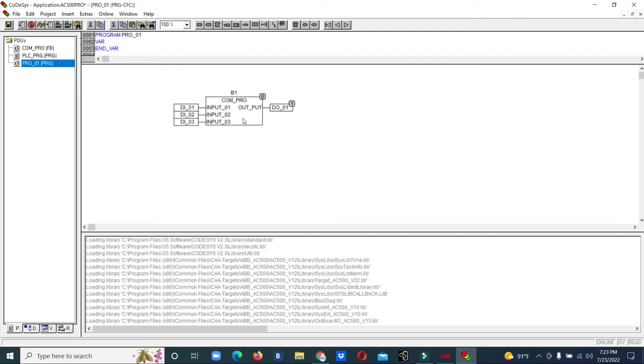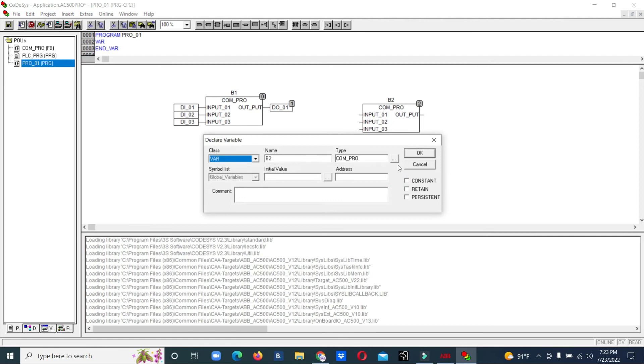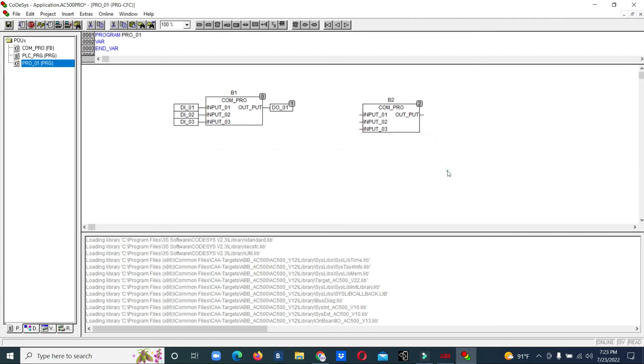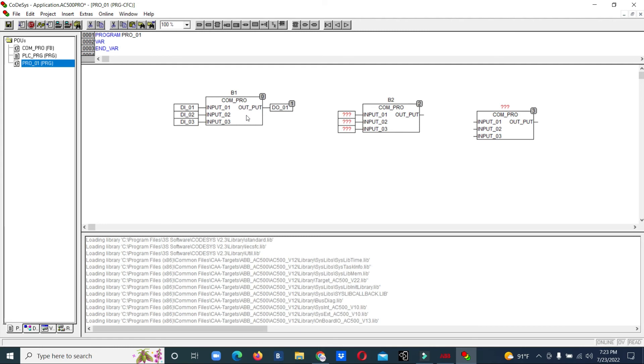If we want to use multiple combinations of three inputs, we go for another block. We can add another 'com_pro' instance and give it another name, like B2. We can assign another three inputs — like 2, 3, 4 or 4, 5, 6 or any combination up to eight inputs. With our one common function block we can achieve programming for all six outputs.